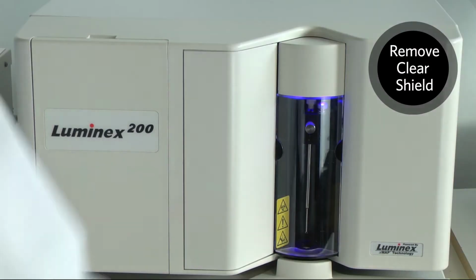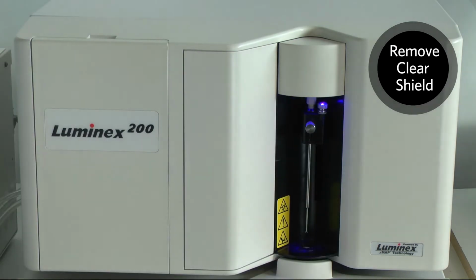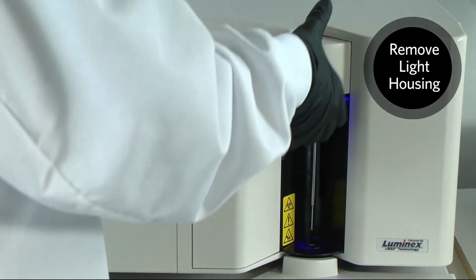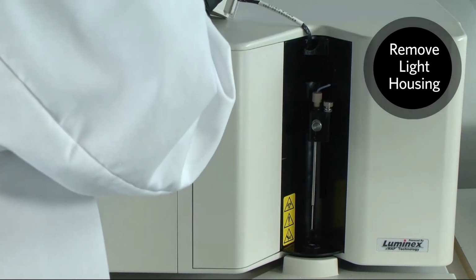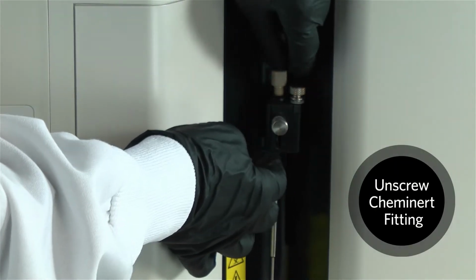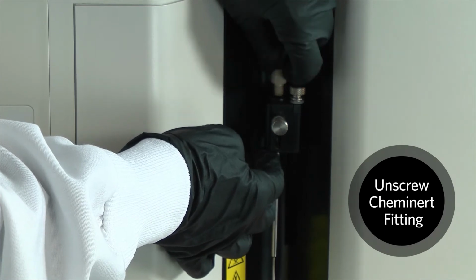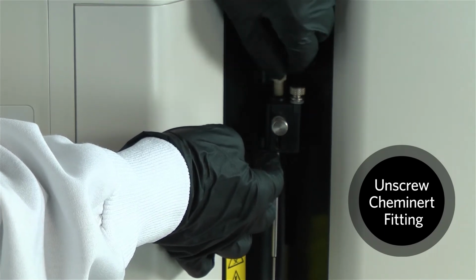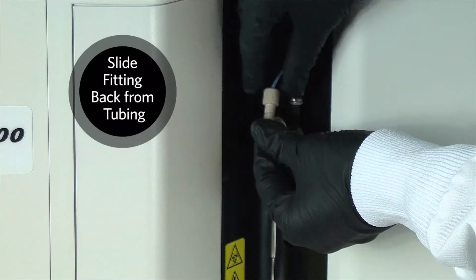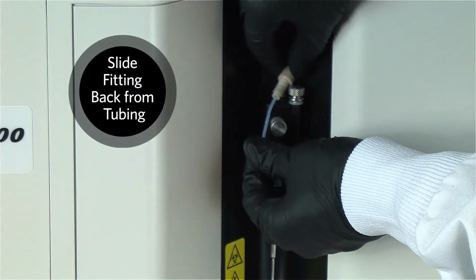First, remove the clear shield in front of the sample probe. Remove the light housing above the sample probe. Unscrew the Cheminert fitting above the sample probe. Slide the Cheminert fitting back from the end of the tubing.